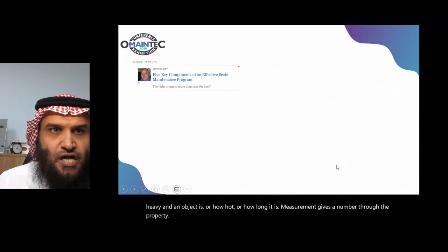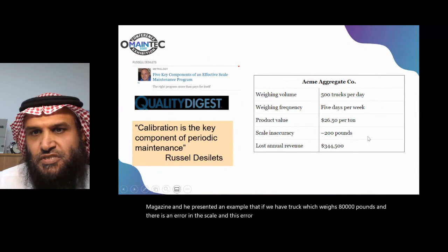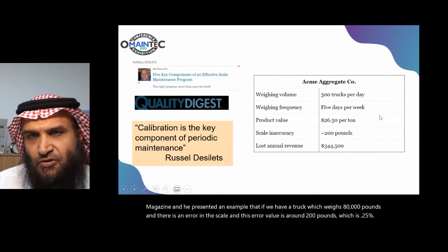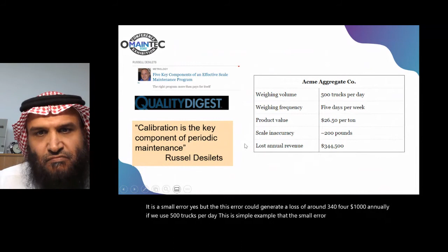Mr. Russell Dizlet wrote an article about 5 key components of an effective scale maintenance, and this could be applicable to all measurement equipment. This article was presented in Quality Digest magazine, and he presented an example that if we have a truck which weighs 80,000 pounds, and there is an error in the scale, and this error value is around 200 pounds, which is 0.25%. It is a small error, yes, but this error could generate a loss of around $344,000 annually if we use 500 trucks per day. This is a simple example that a small error in measurement equipment might be translated into many thousands or millions of dollars.